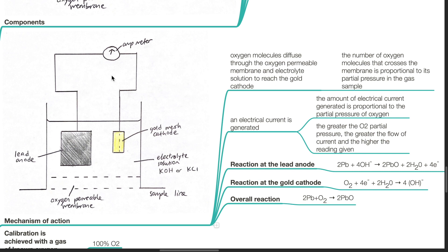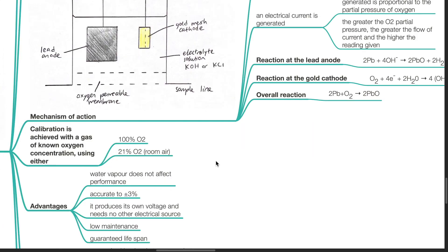Reaction at the lead anode: 2Pb + 4OH⁻ → 2PbO + 2H₂O + 4e⁻. Reaction at the gold cathode: O₂ + 4e⁻ + 2H₂O → 4OH⁻. And the overall reaction produces 2PbO. Calibration is achieved with a gas of known oxygen concentration, using either 100% oxygen or 21% oxygen.